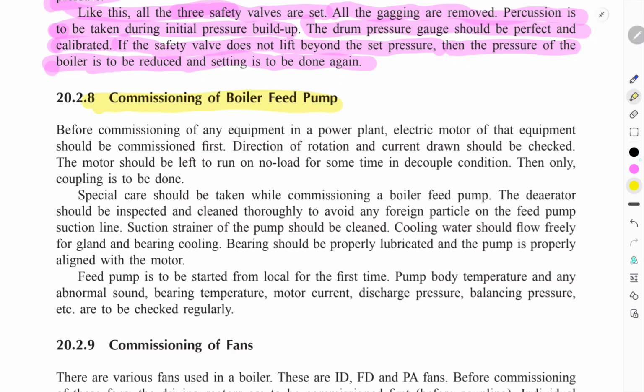Okay. Before the commissioning of any equipment in a power plant with an electrical motor, the motor should be commissioned first. The direction of rotation and current drawing should be checked. The motor should be run on no load for some time in decoupled condition. Only then is the coupling to be done.